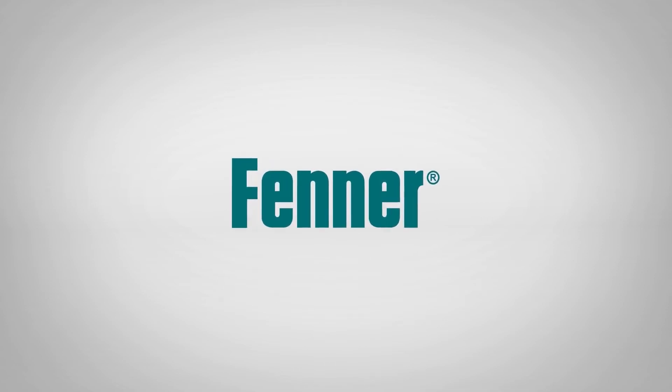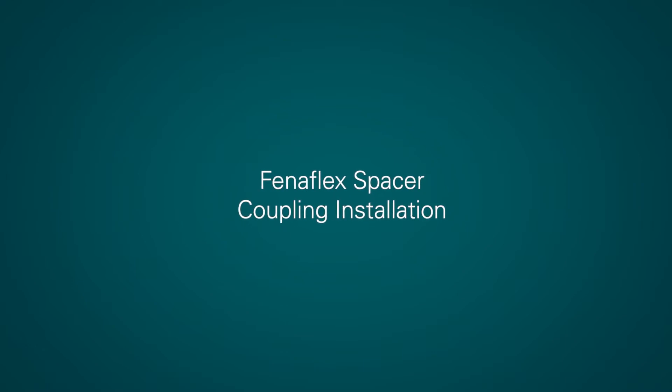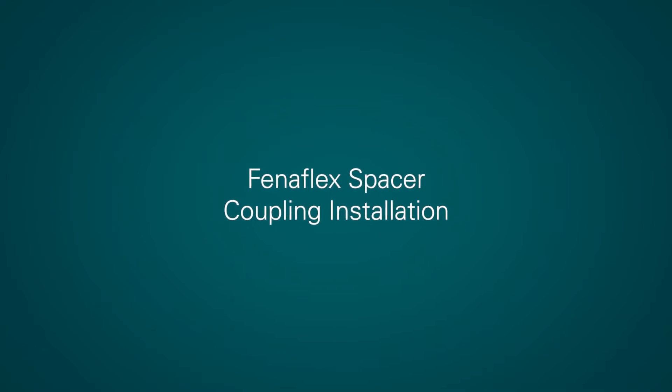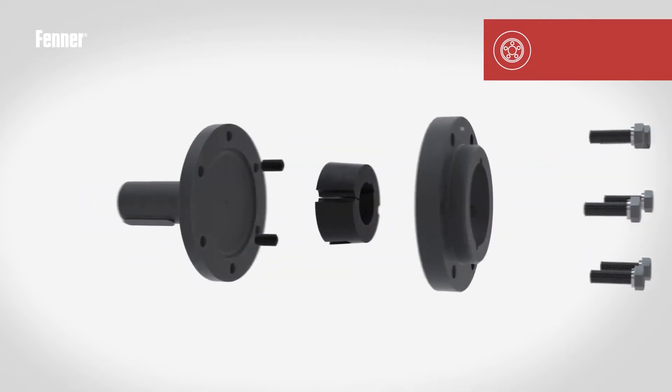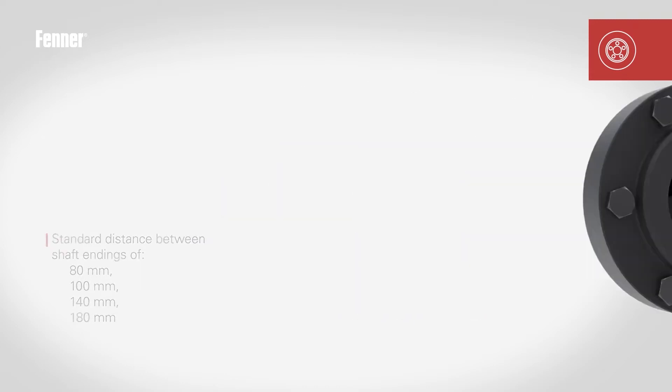The Fenaflex spacer coupling is designed primarily for the pump industry, and the design allows for the prime mover or driven machine shafts to be moved axially without disturbing either machine. The coupling is designed to accommodate standard distance between shaft end dimensions of 80, 100, 140 and 180 millimetres.